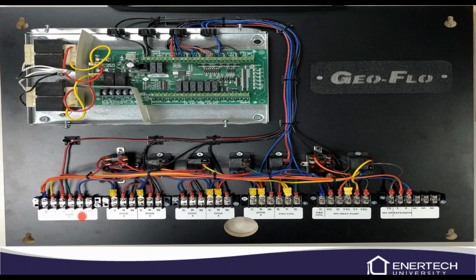Now, as you can see on here, we've got 6 zones available here for use. If you need more than that, we do have an expansion that you can tie on and add 6 more zones. Now, on this zone control, one thing we need to remember is that this HydroConnect can handle 1 fan coil and 5 radiant zones. So if you have 2 fan coils in 1 radiant zone, you're going to have 2 of these panels so you can handle your air handlers. So just keep that in mind. That's one of the nuances of this equipment.